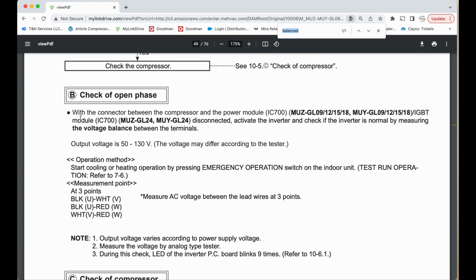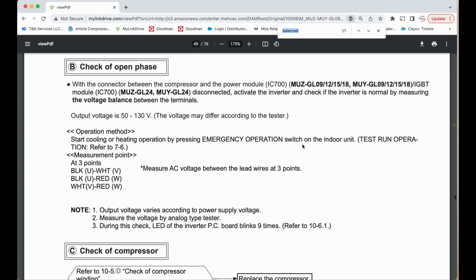It tells you, with the connector between the compressor and the power board disconnected, go ahead and activate the unit, meaning use a test run like we did. At that point we're going to check the voltage between U, V, and W, as I showed in the video. We should have anywhere between 50 and 100 volts or 130 volts AC. And in the video we had 49.3, somewhere around there. But it also says right here the voltage may differ according to the tester. So I knew that unit was working, so that 49.3, 49.8 was right along this 50 volt line. That is how you check the compressor for balanced voltages.